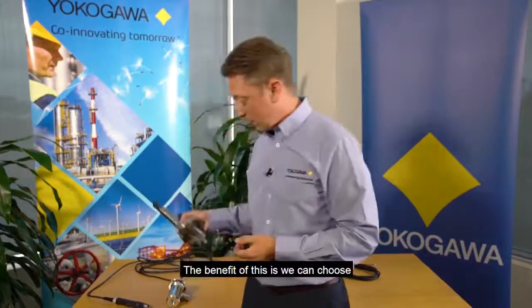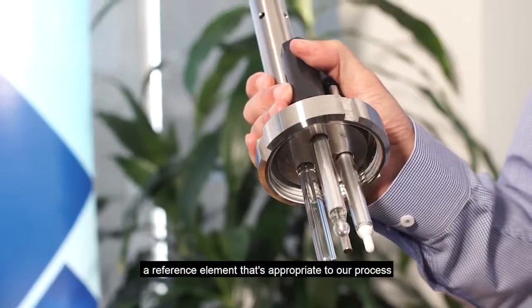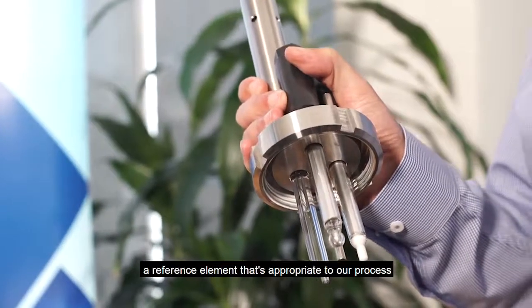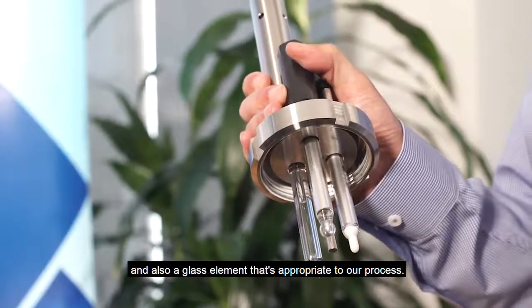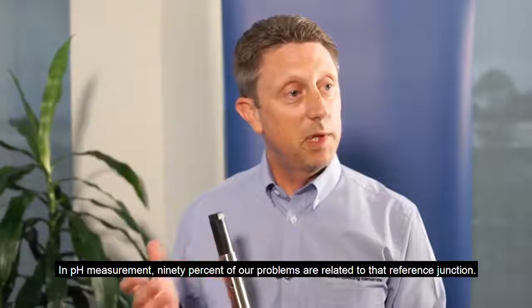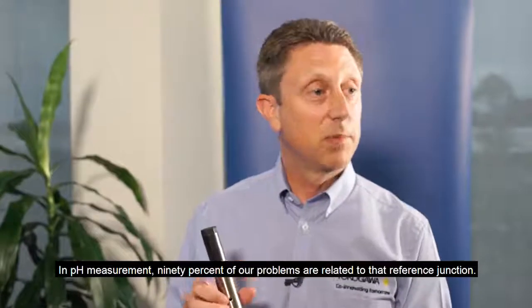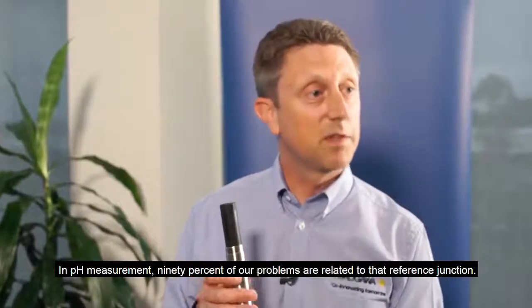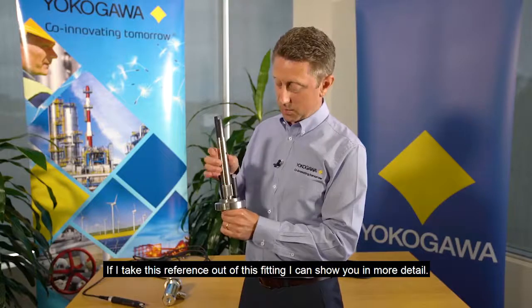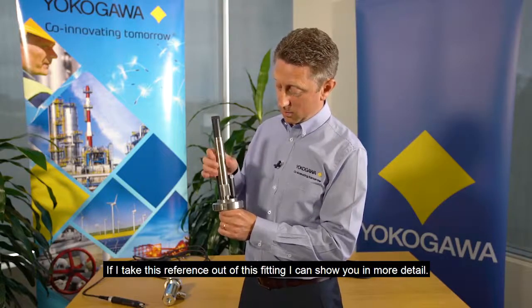The benefit of separate elements is we can choose a reference element appropriate to our process, and also a glass element appropriate to our process. In pH measurement, 90% of our problems are related to that reference junction. If I take this reference out of this fitting, I can show you in more detail.